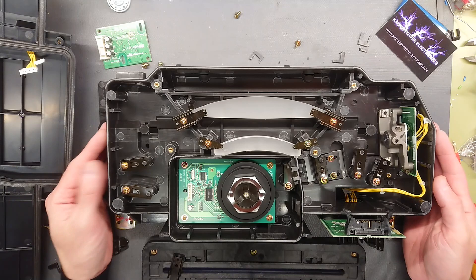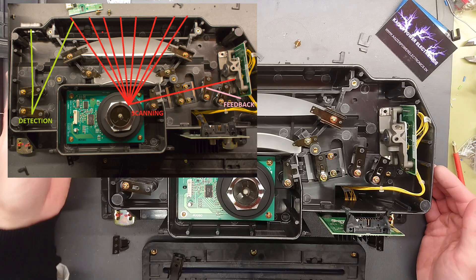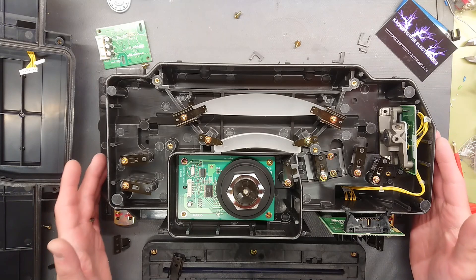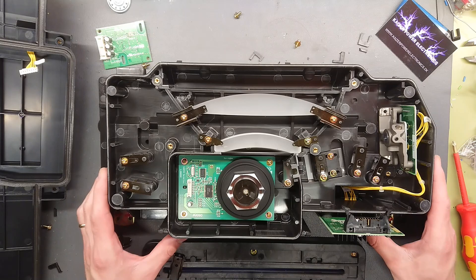I hope you enjoyed this teardown of the laser module and saw that it is in fact not that complex. It is just a matter of a rotating motor at a certain speed in order to get a scanning line from a simple laser beam. That's all there is to it — one laser beam shot at a time, at one XY position of the image plate. And then the PMT, which we will take a look at in part three, will read out the grayscale value — something like 12 to 16 bit resolution. Thank you for watching, and until next time, see ya.